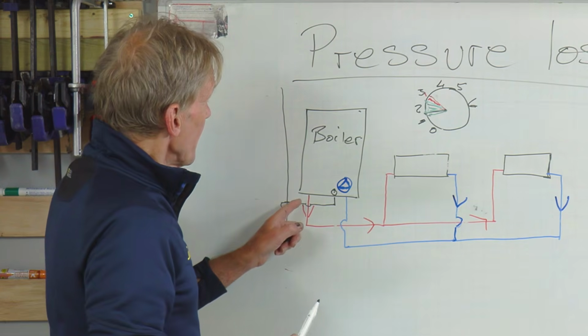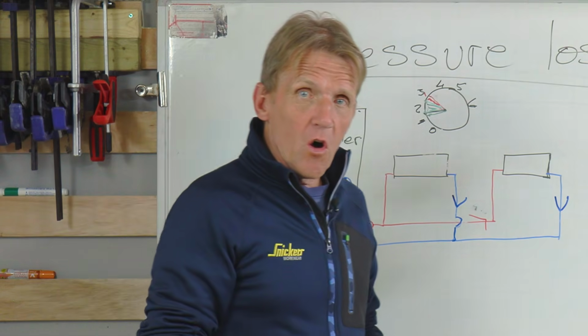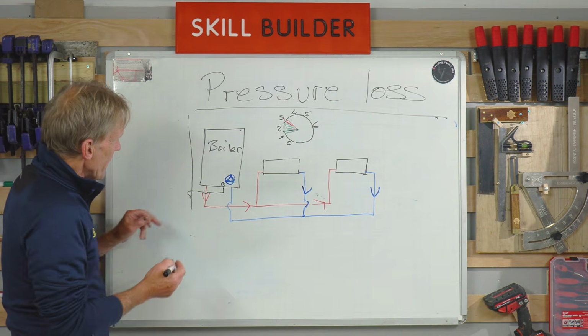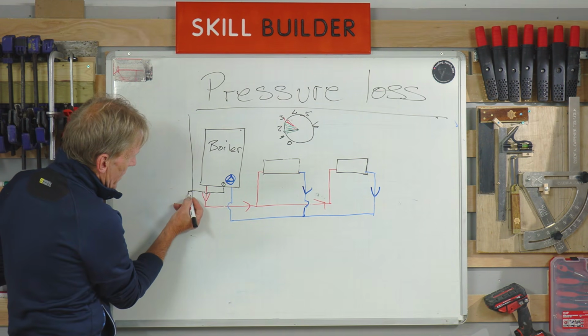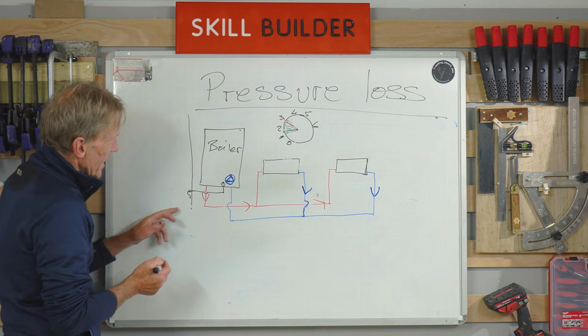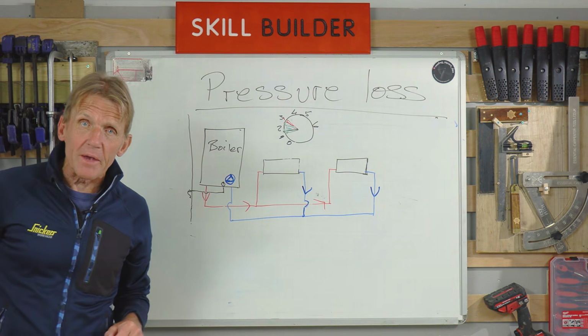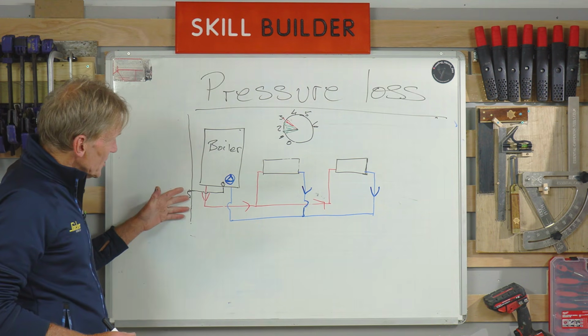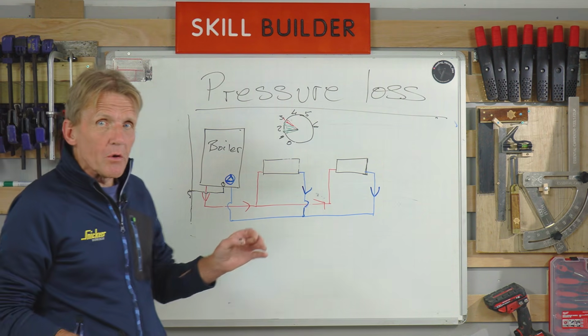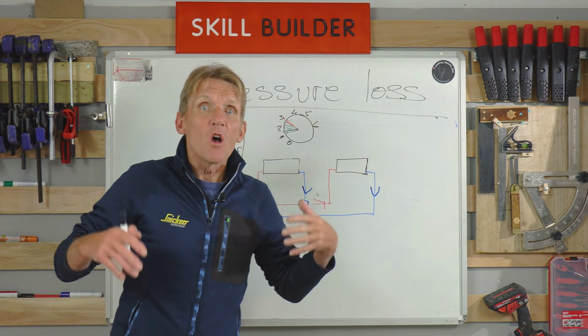And the reason for that is that there'd be hot water coming out of here, and if somebody's walking past there, you don't want them to get a face full of hot water if this boiler suddenly decides it needs to relieve a little bit of its pressure. So that little safety device, that little way that we turn that pipe round or put some kind of cap on it so that it sprays against the wall, is very, very useful, because if there's any water coming out of it, we may see a kind of staining or a wet patch on the wall where that water's been coming out. Sometimes we won't, because sometimes it's just dripping out little bit by little bit over the course of a week.